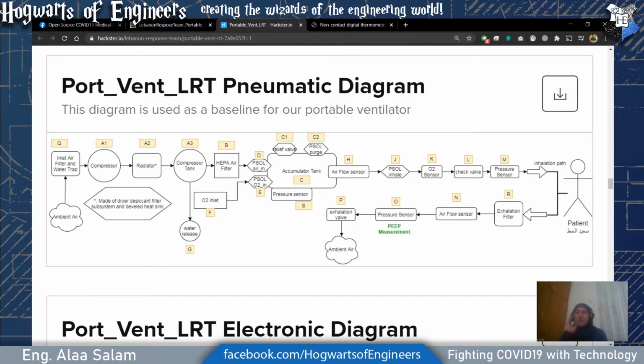So you have to supply a particular voltage for it to move at specific notches. A PSOL valve is like a servo motor, but it controls a valve. So we move the motor or the actual piston of the valve at specific lengths so that it can open or close to control the amount of air coming in. This is for the PSOL air in. For PSOL oxygen in, it controls the level of oxygen.